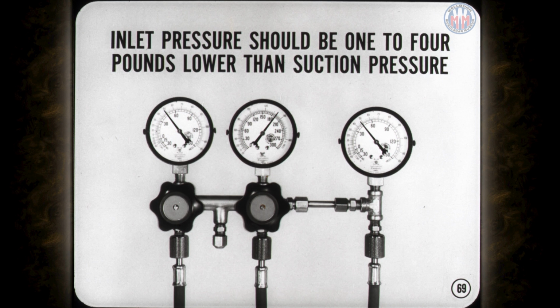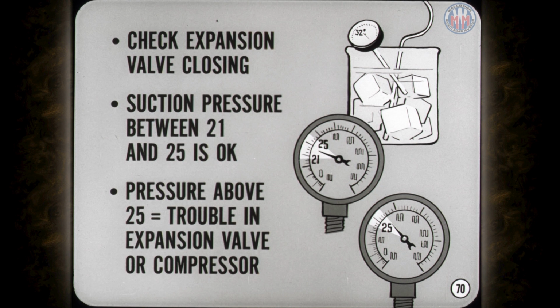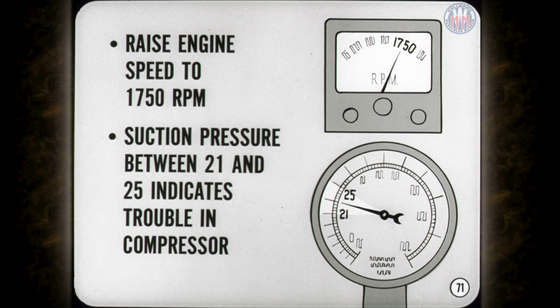Assuming that the suction pressure is okay, you then read compressor inlet pressure to check the EPR valve for proper opening. If the valve works properly, inlet pressure should read between 1 and 4 pounds lower than suction pressure. More than a 4-pound pressure drop calls for a new EPR valve. Next, we check the expansion valve for closing by immersing 5 inches of its thermal bulb in a container of ice and water at 32 degrees. When the valve closes, a suction pressure between 21 and 25 is okay. If the pressure stays above 25, the trouble may be either in the expansion valve or the compressor.